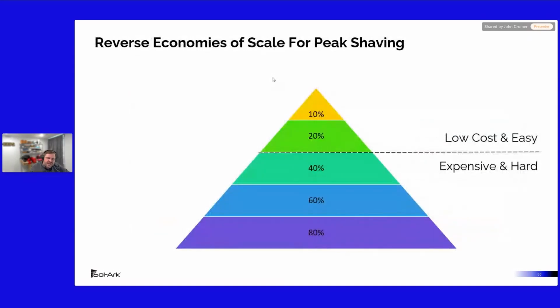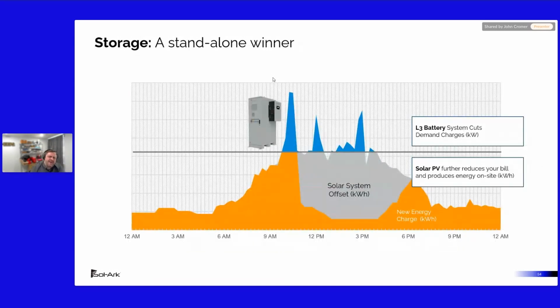But the takeaway is that unlike solar, where you need to offset 100% of the bill or cover the entirety of the rooftop, a small commercial project can be very low cost—the customer can write a check and buy it. It can also be easy to install, since you're not getting into backup power or whole building backup applications. Just by connecting it and lowering demand charges, that's a low cost, easy to install project, which might look like just one battery cabinet and one inverter.